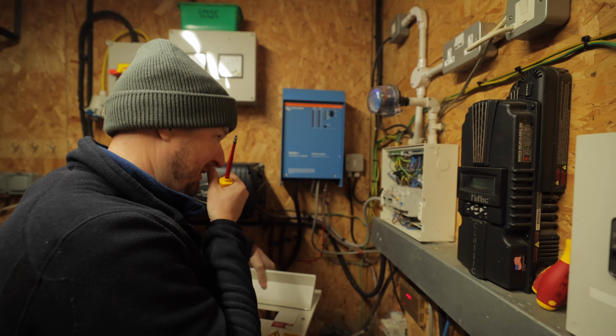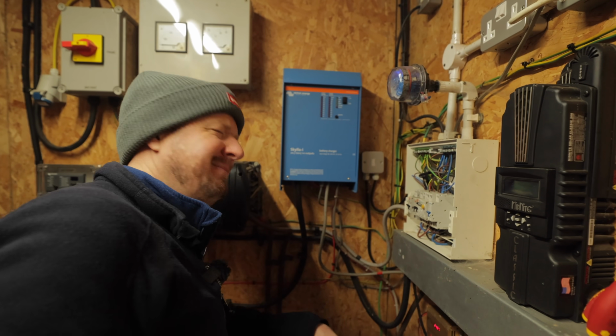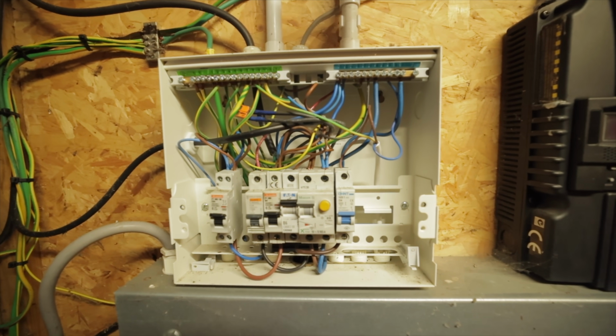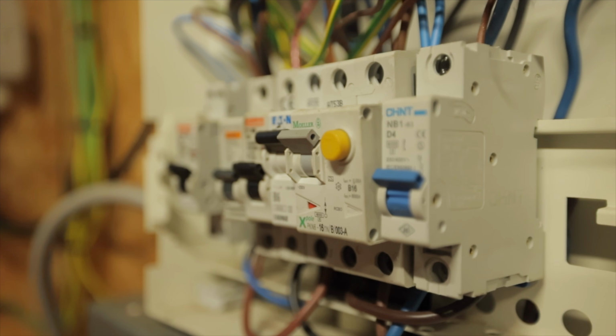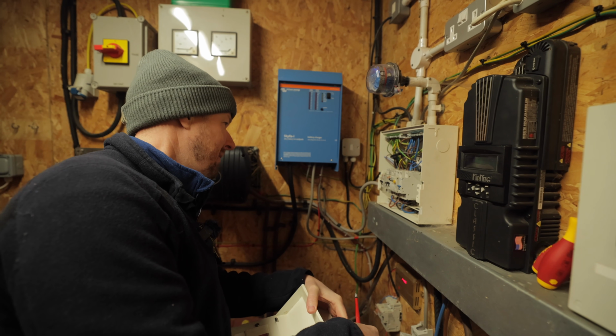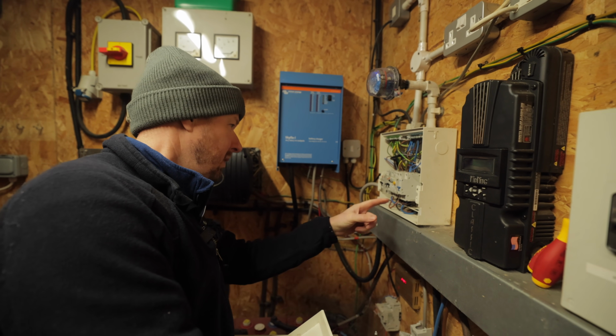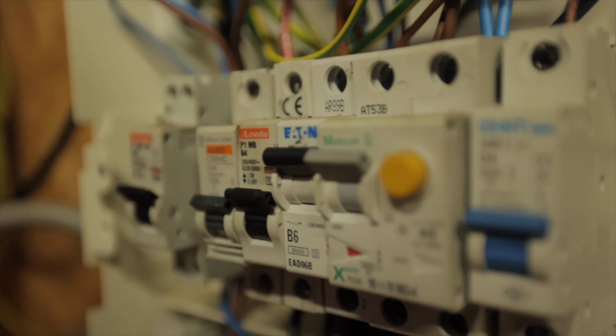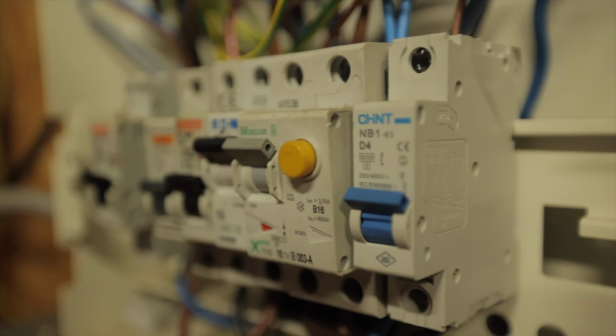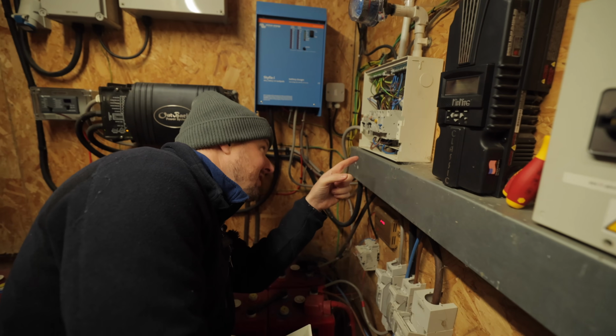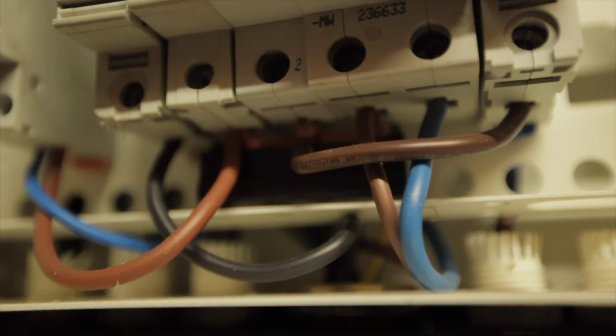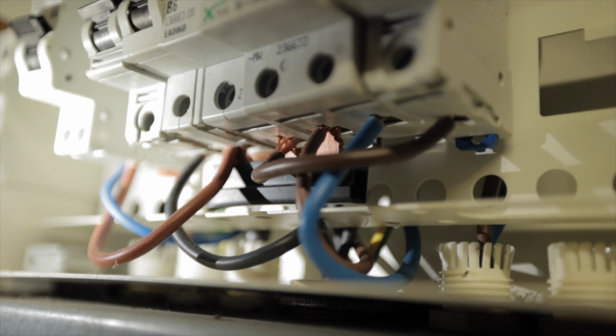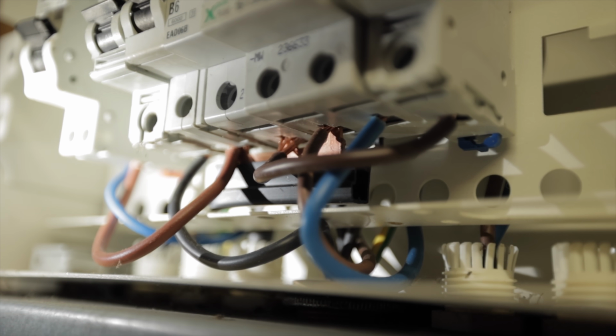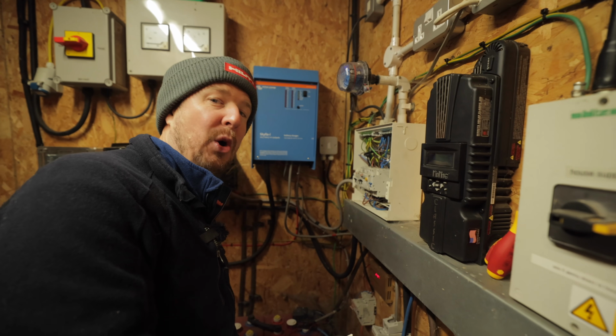Yeah, here we go, classic example. Neat or not neat? Not neat. That is absolutely hideous, like it's just been bodged in by somebody who sort of knew what they were doing by the looks of it, but didn't really care about neatness. They've used five different brands of circuit breaker. There's no main switch in here. They've just used these wire loops as some kind of bus bar system, but it's all very, very confusing. Look at the amount of exposed copper underneath there. That is crazy. Not a good start.